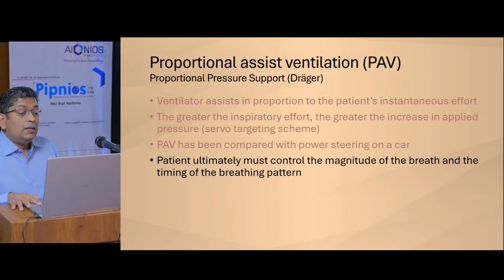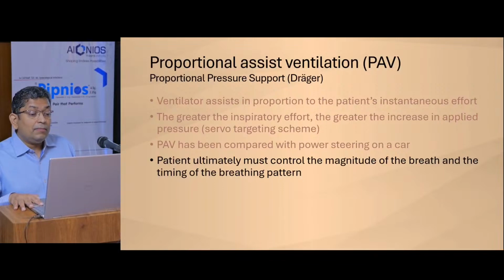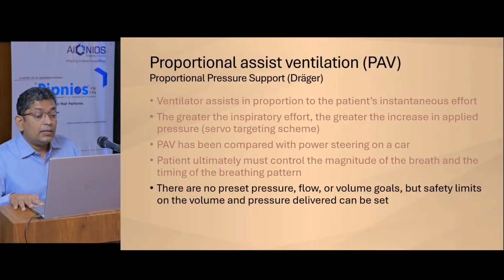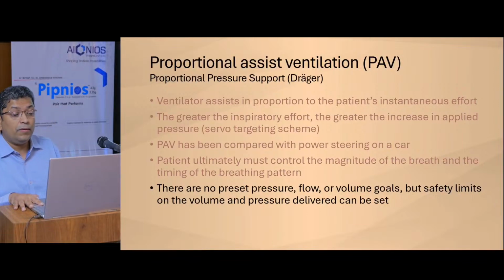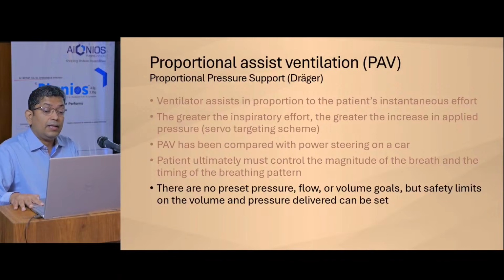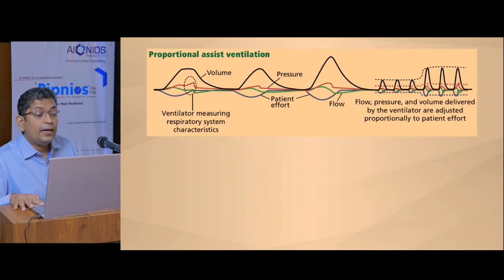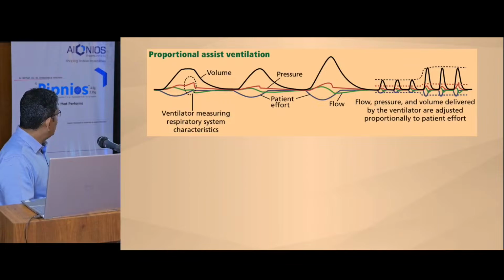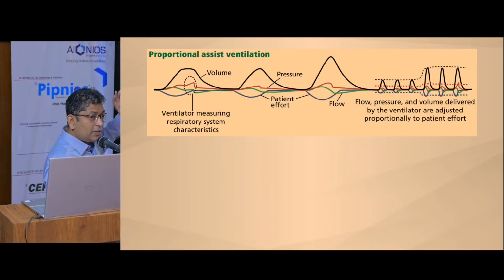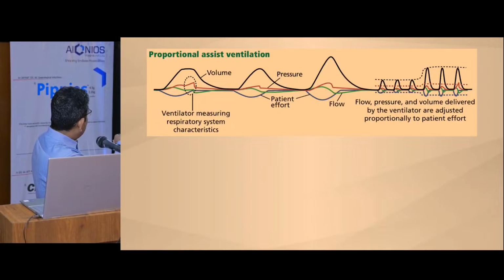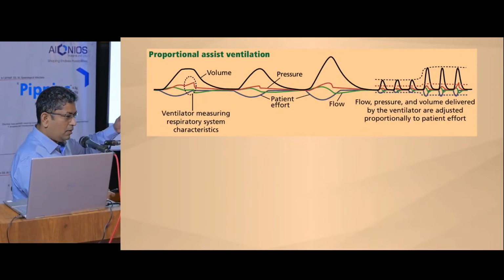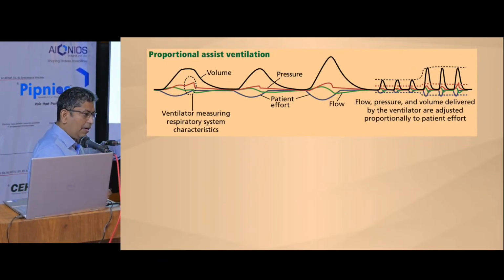So the patient can ultimately control the magnitude of breath, the timing, and the breathing pattern. Okay, it's a support mode. So it's flow cycled, and there are no preset pressure, flow, or volume goals, but safety limits are there. Now, how does it do this? In the first couple of breaths, it checks the respiratory system characteristics, looks at the resistance, the compliance, and it also looks at the patient effort.